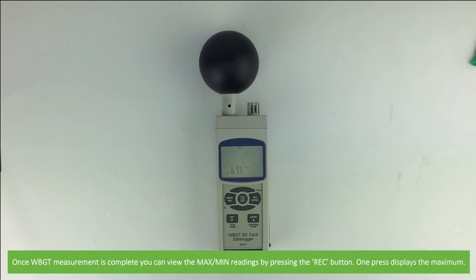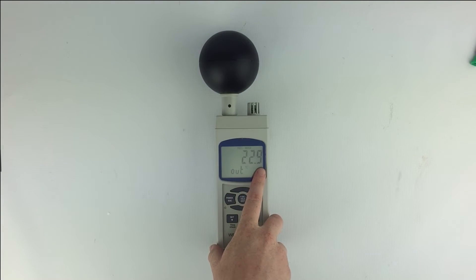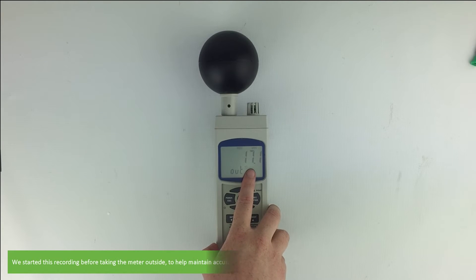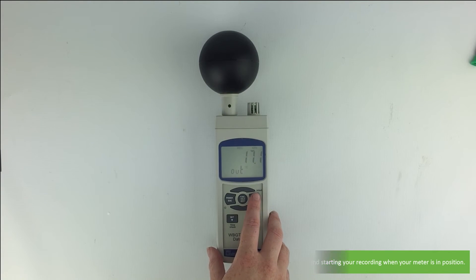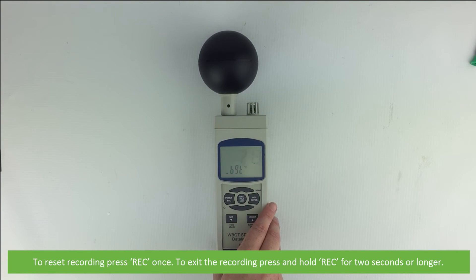Once the wet bulb globe temperature measurement is complete, you can view the maximum and minimum readings by pressing the REC button. One press displays the maximum and a second press displays the minimum. We started recording before taking the meter outside — to help with accurate data collection we recommend starting your recording when your meter is in position. To reset recording press REC once, and to exit the recording press and hold REC for about two seconds or longer.